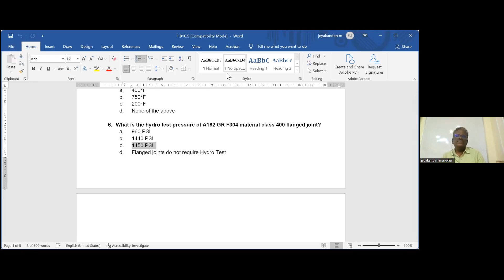Okay, so in the code book: flange joints may be subject to the hydrostatic test at a pressure 1.5 times the 100 degree rating, rounded up to the next higher 25 psi.